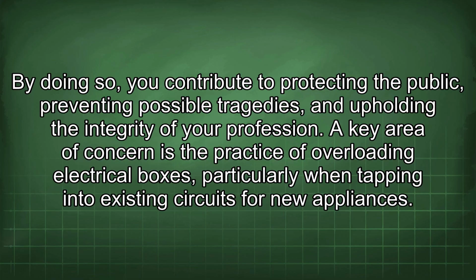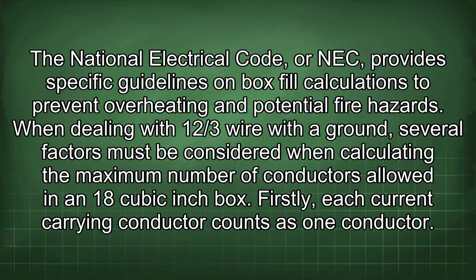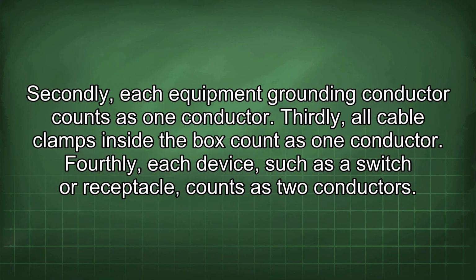A key area of concern is the practice of overloading electrical boxes, particularly when tapping into existing circuits for new appliances. The National Electrical Code, or NEC, provides specific guidelines on box fill calculations to prevent overheating and potential fire hazards. When dealing with 12/3 wire with a ground, several factors must be considered when calculating the maximum number of conductors allowed in an 18 cubic inch box. Firstly, each current carrying conductor counts as one conductor. Secondly, each equipment grounding conductor counts as one conductor. Thirdly, all cable clamps inside the box count as one conductor. Fourthly, each device, such as a switch or receptacle, counts as two conductors.